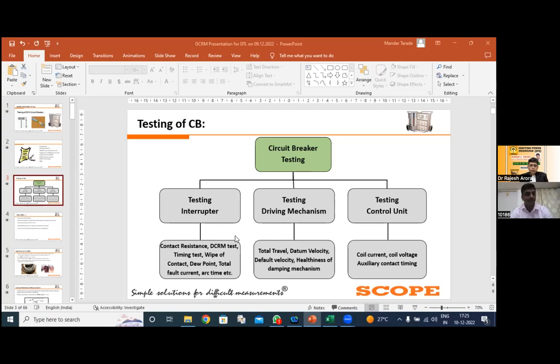Next one is the DCRM test. In the DCRM test, basically we perform the dual operation, that is the CO operation or the dynamic operation. According to the duty cycle defined by the IEC standard, we give the delay TCO for the mechanism, and accordingly we perform the DCRM test and check the behavior of the arcing contact as well as the main contact. Moving further, we perform the timing test. With the help of the timing test, we can check whether the results we are getting are as per the standard or as per the limits of the manufacturer or not.